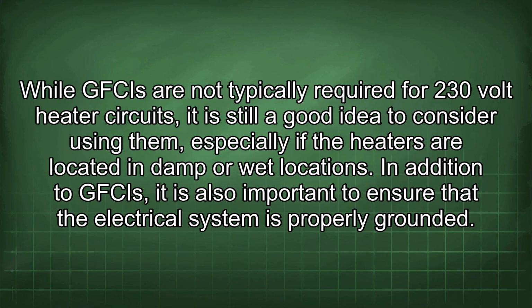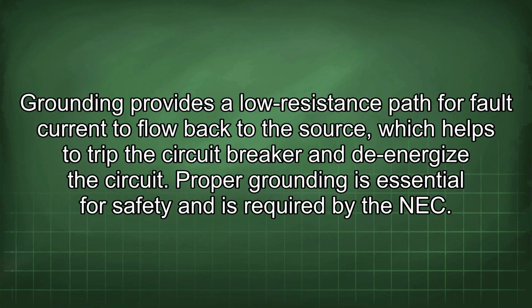While GFCIs are not typically required for 230-volt heater circuits, it is still a good idea to consider using them, especially if the heaters are located in damp or wet locations. In addition to GFCIs, it is also important to ensure that the electrical system is properly grounded. Grounding provides a lower resistance path for fault current to flow back to the source, which helps to trip the circuit breaker and de-energize the circuit. Proper grounding is essential for safety and is required by the NEC.